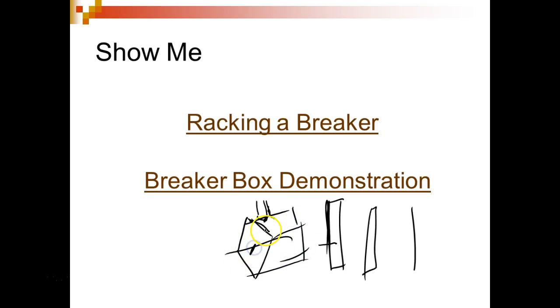And then you'll have the breaker. Well, these things have to be worked on, so they got to get that thing out. They'll have a screw down in the bottom, and they turn that handle to screw it out until they get it far enough. Most of the time they'll have a cart that they line up, pull it in, and once it breaks loose off the screw, they pull it out onto that cart and take it off to work on it. That's what we call unracking a breaker.